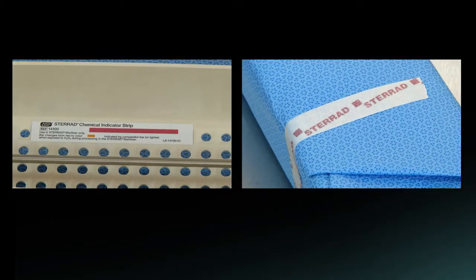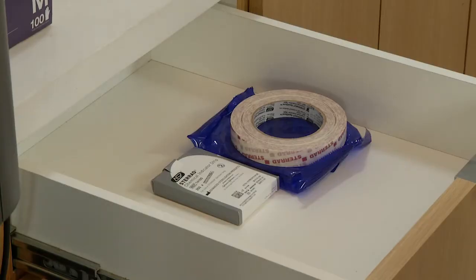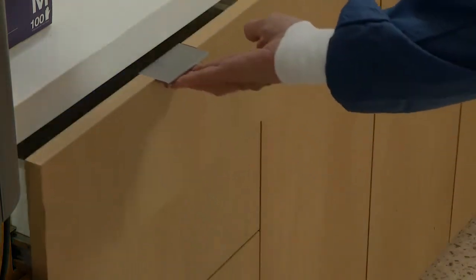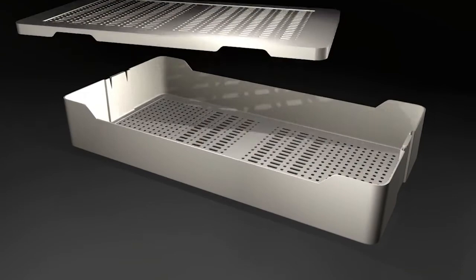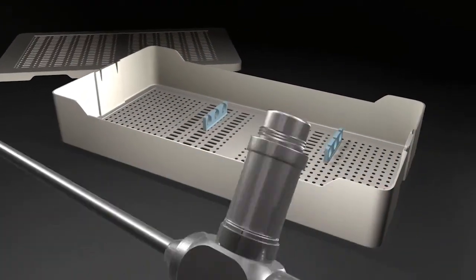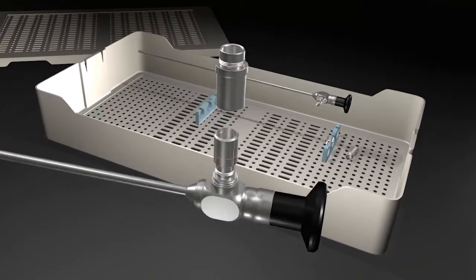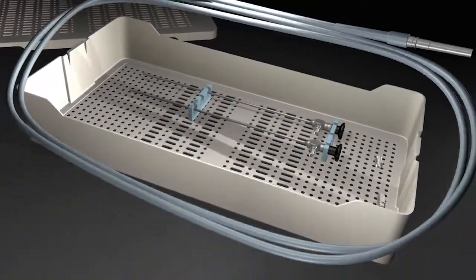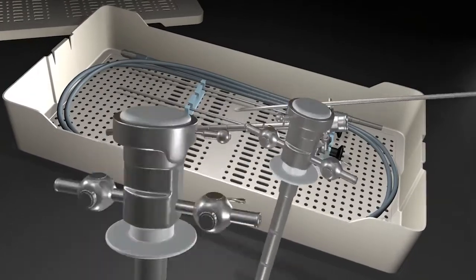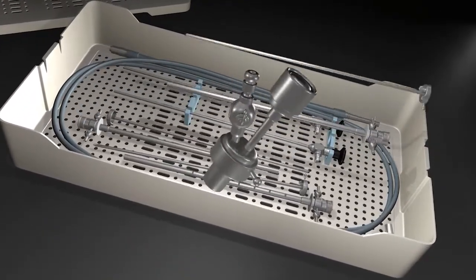The STERRAD chemical indicator strips and STERRAD SealSure chemical indicator tape change from red to yellow when exposed to hydrogen peroxide. Yellow indicates processed and red indicates unprocessed. Be sure to store the STERRAD SealSure chemical indicator strip box and STERRAD SealSure chemical indicator tape away from heat and light. Detailed information on loading and packaging can be found in your user's guide, but the following are some basic guidelines. Arrange items within a tray to ensure proper diffusion of H2O2 throughout the load. Do not stack instruments within trays or containers.